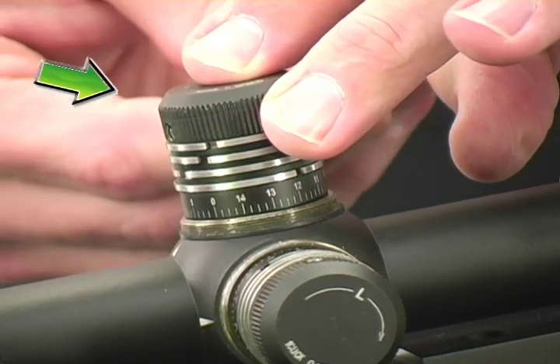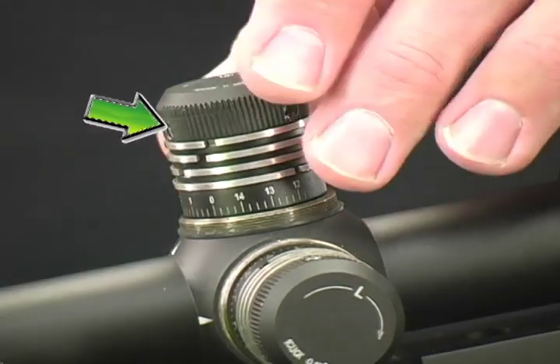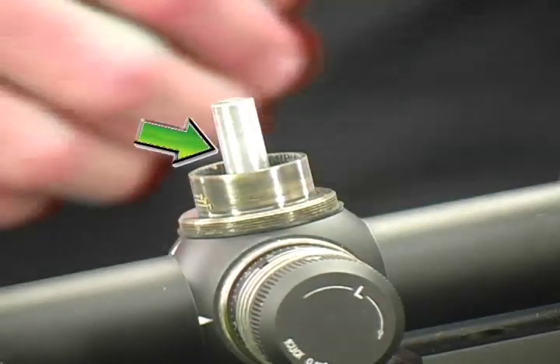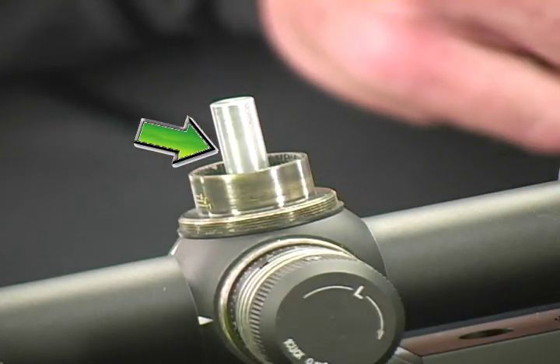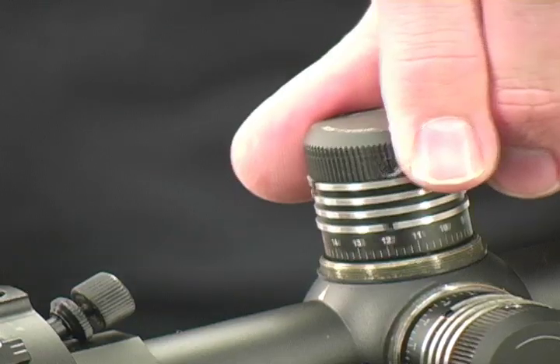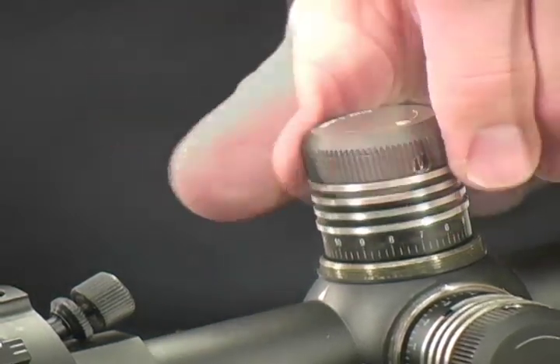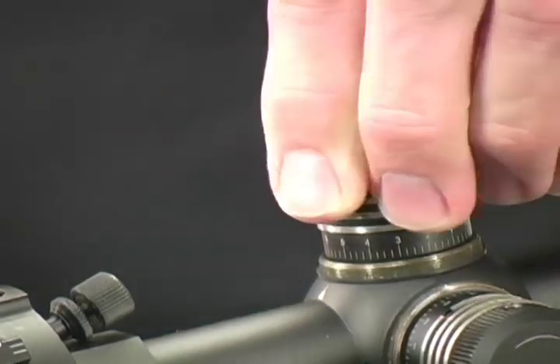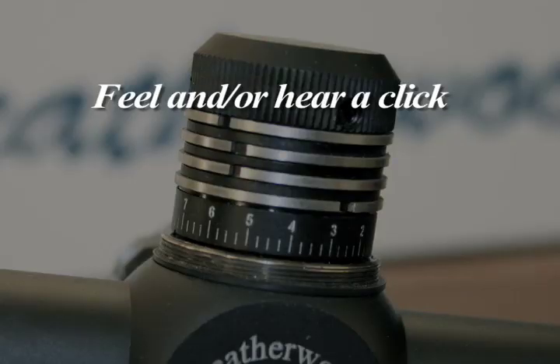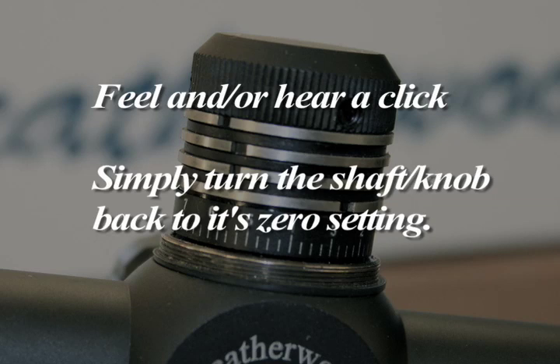At this point, set your first zero. Once the first zero is set, loosen the 3 set screws again, but be careful not to turn the adjusting shaft. The initial zero will be deviated if the adjusting shaft is turned. You'll know if the adjusting shaft has turned if you hear and/or feel the knob click. If the shaft does turn, simply turn the shaft back to its zero.